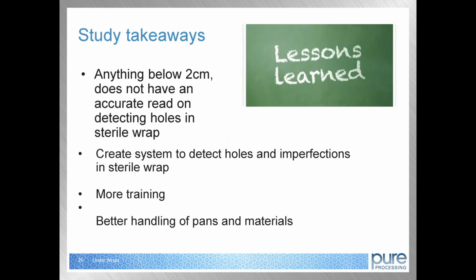Because what we don't want is to be sending up a pan that has a hole and can be compromised. Anything below 2 centimeters is like a pinhole, and just that size of a hole can transmit contamination. If you have holes in a sterilized surgical wrap and they're not identified, the patients can be exposed to dangerous pathogens. The other thing is, if it does have a hole and it gets ready to go onto the back table, it has to be taken down, and then it compromises the procedure. It compromises the time that the patient is under anesthesia, and it also compromises the time you're going to need to sterilize the pan, because that pan is going to have to go down. It's going to have to be re-sterilized because it has now broken the barrier and is no longer sterile.